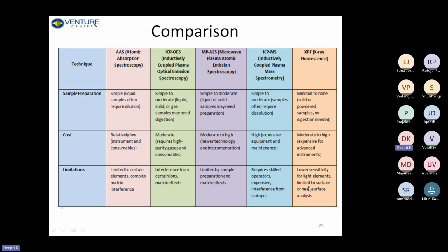XRF has lower sensitivity for lighter elements, and it is limited to surface or near surface analysis only. Okay, it cannot do in-depth. If you want to measure a biological sample of a few millimeters thickness, element analysis of the deeper layers cannot be performed.